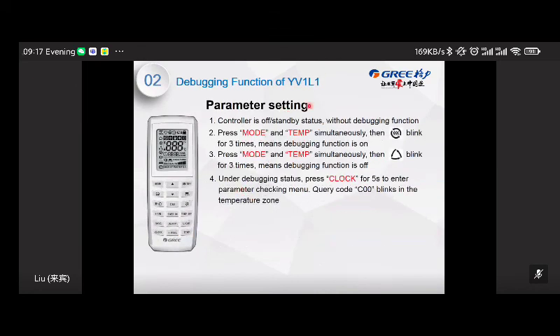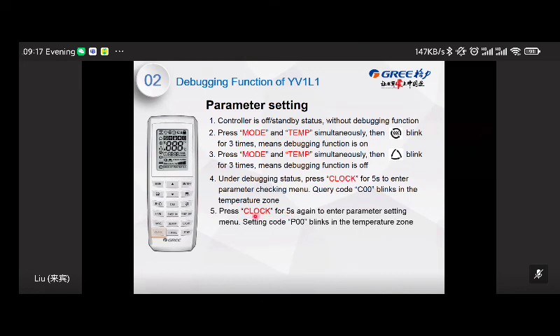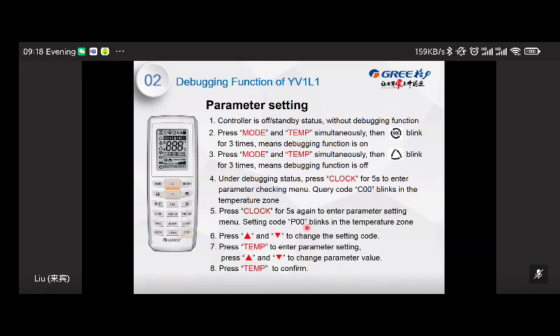And for the parameter setting, it's similar. Press the mode and temperature buttons, and then you can see this icon blink. That means the debugging function is on. Then press the clock for 5 seconds, and you can see C00. That means checking. However, if you want to shift to the setting, press the clock for another 5 seconds. This step is different from the previous one. Then you can see P00. That means program setting is activated. Then you can just change the value and press the temperature button to confirm and exit.